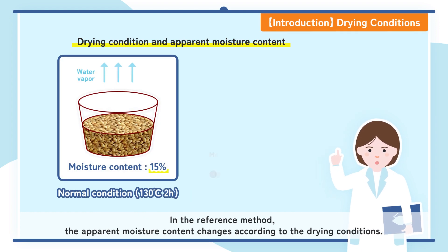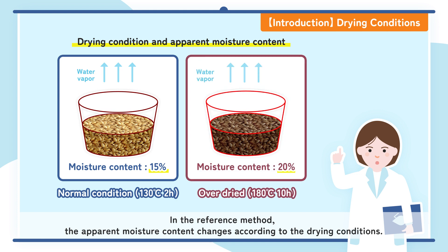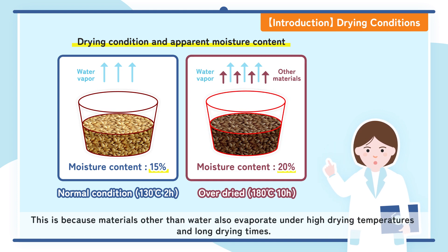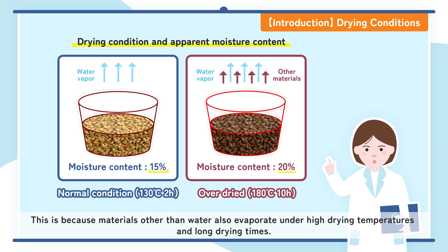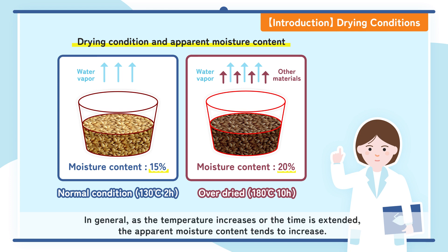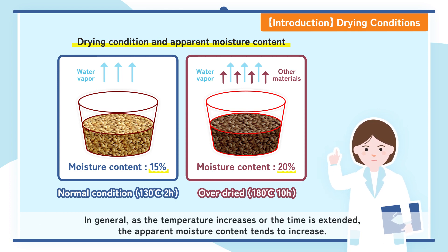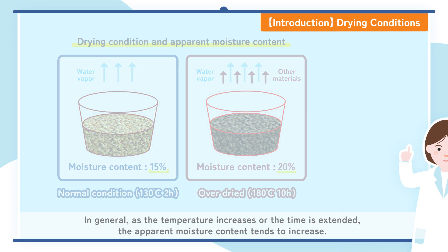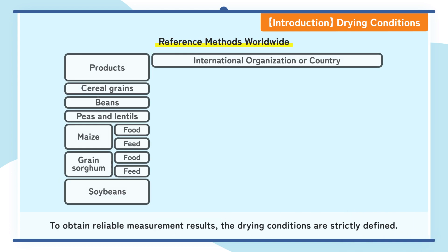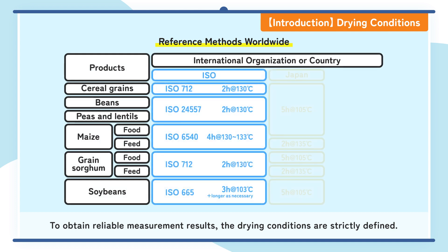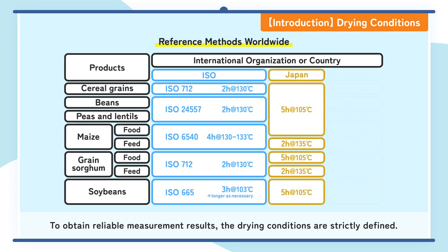In the reference method, the apparent moisture content changes according to the drying conditions. This is because materials other than water also evaporate under high drying temperatures and long drying times. In general, as the temperature increases or the time is extended, the apparent moisture content tends to increase. To obtain reliable measurement results, the drying conditions are strictly defined.